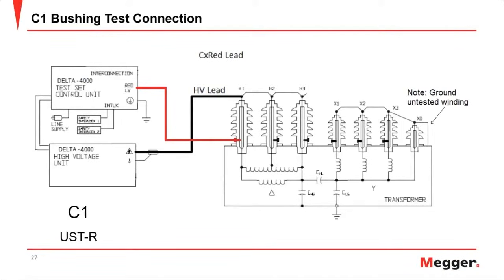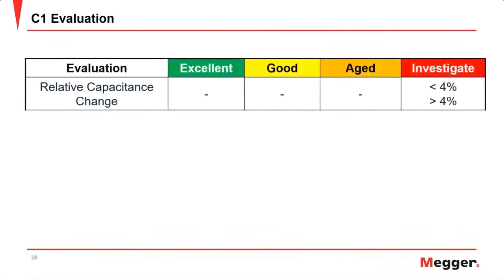So now that we've hooked up the test set and we've performed a USTR test, we get a result, and now we need to evaluate that. We have a few different criteria that we can look at for evaluation. First being capacitance, and we want to look at the relative capacitance change. When I say relative, I am talking about the capacitance that is stamped on the bushing nameplate. So if it has changed by greater than or less than 4%, we see this as a reason for that bushing to undergo additional evaluation.